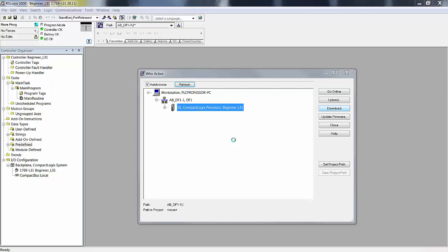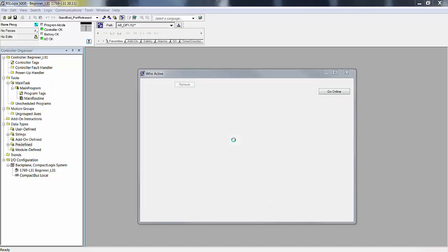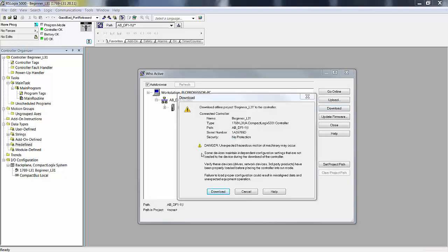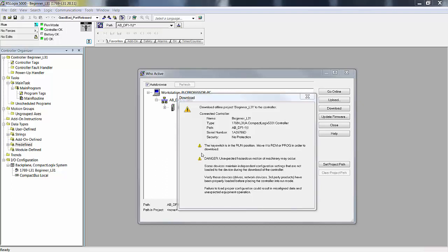That's the problem with RS-232. Even at 38,400, it is slow. You spend a lot of time waiting. Now this is okay if you're learning, okay? Connect a controller. So evidently it's only going to show me if I'm in the run mode. I just flipped it into the run mode. See? Key switch is in the run position. Now it says remote run mode. There is a little variation in this message.